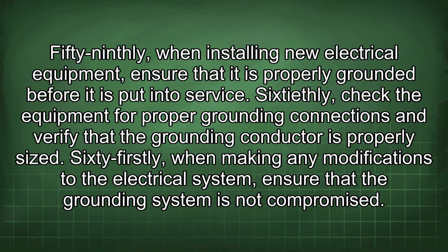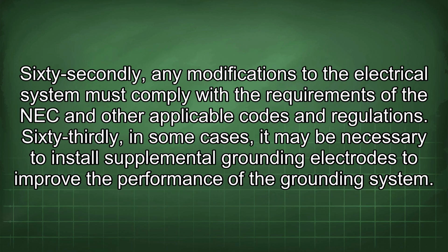59thly, when installing new electrical equipment, ensure that it is properly grounded before it is put into service. 60thly, check the equipment for proper grounding connections and verify that the grounding conductor is properly sized. 61stly, when making any modifications to the electrical system, ensure that the grounding system is not compromised.